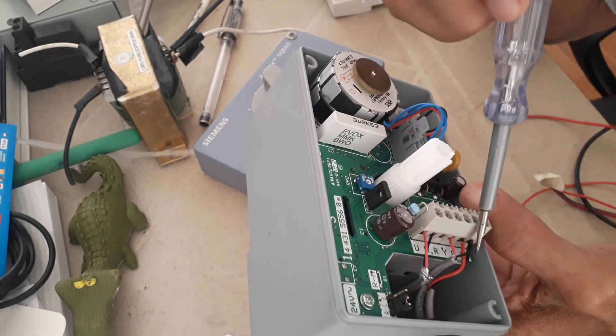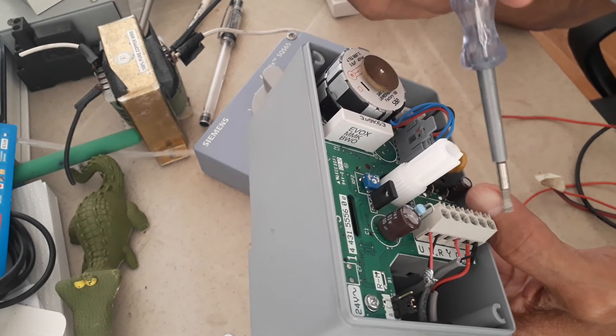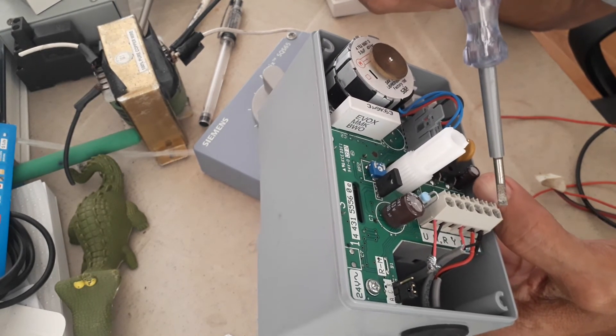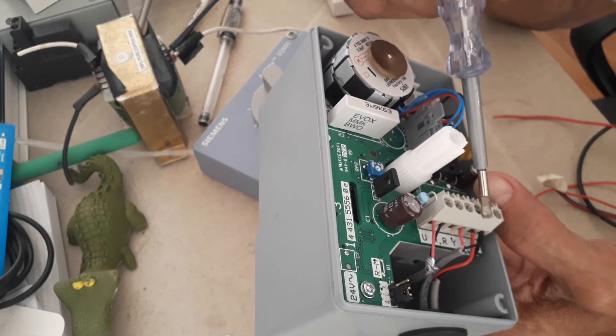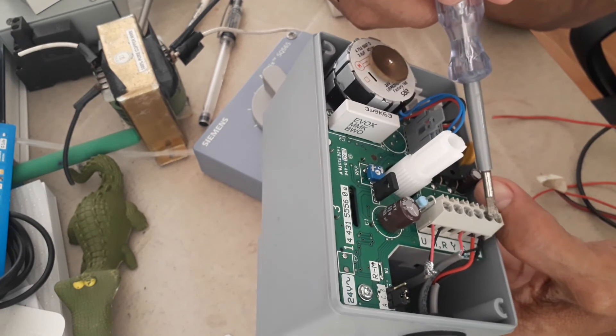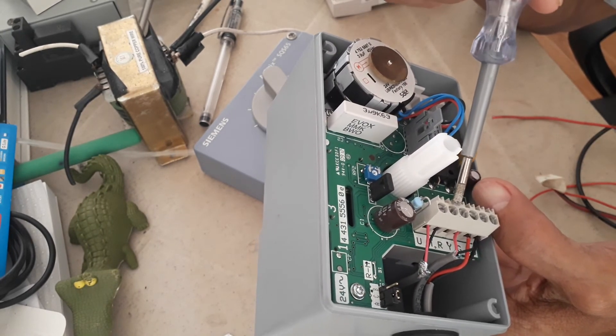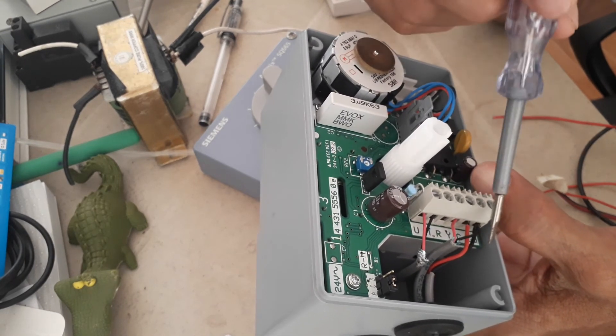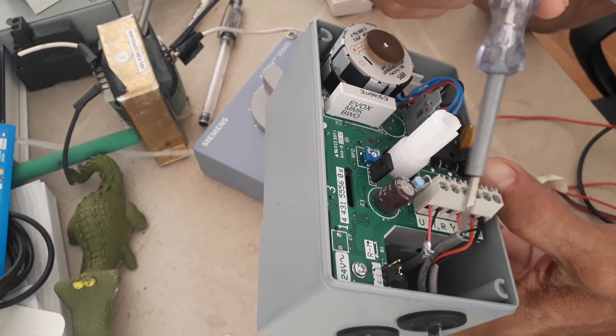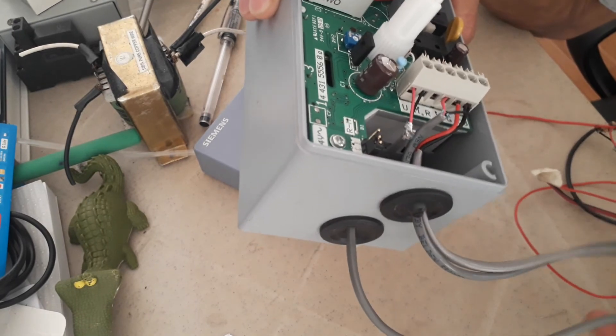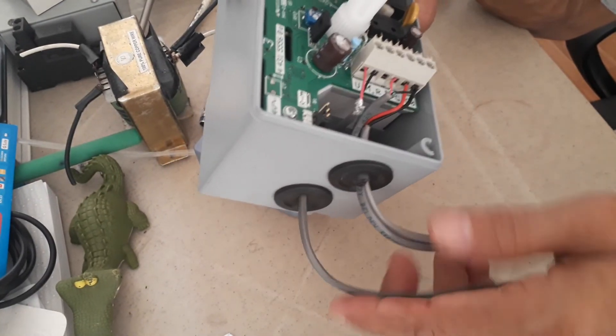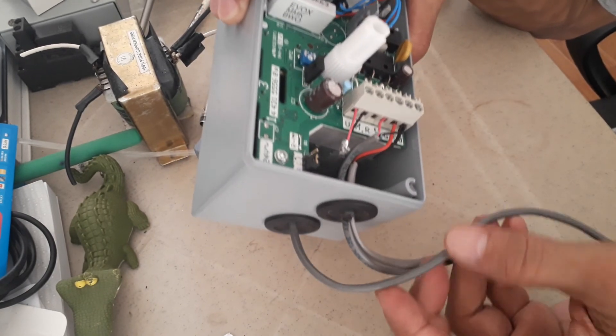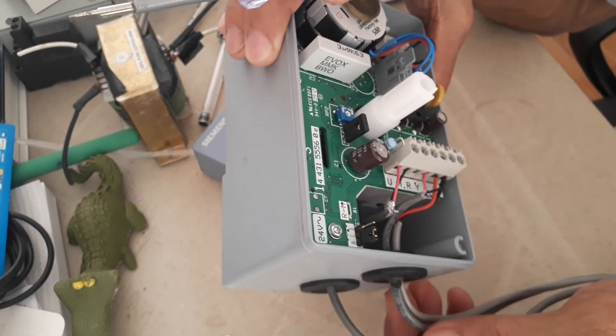24 volts will be coming from your control transformer. Then, the signal will be coming from your DDC analog output signal or analog output control based on your control logic program. Then, the feedback will go to one of the analog inputs of your IO module. This is how are you going to pull cable. Make sure you will pull BMS cable the correct quantity. Because if you forget one cable, it is a big headache when you are ready to do the testing and commissioning.